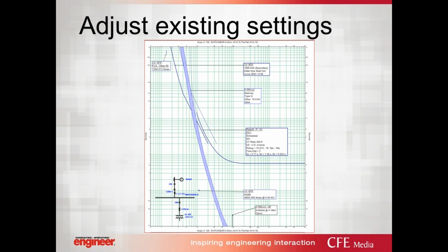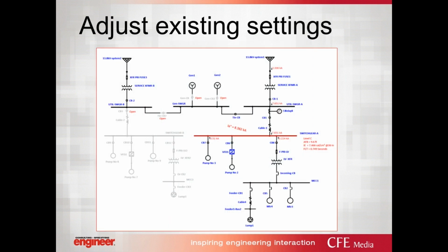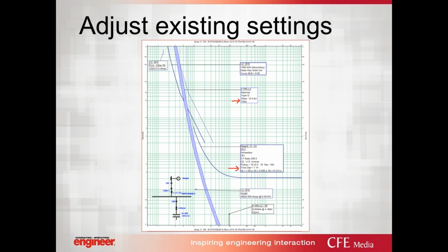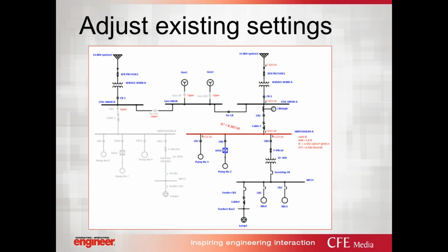As you see here, the fuse is rated 200 amps, and it's protecting the transformer, but I am still able to move or adjusting this fuse to take advantage of the settings to reduce the incident energy. Let's look at the results based on what I have. At this point, based on 200 amps fuse at this bus, I have 7.5 calorie, and next one, I'm going to move the fuse to make it 150 amps, and then I will reduce that one to about 3.35 calorie per centimeter square.